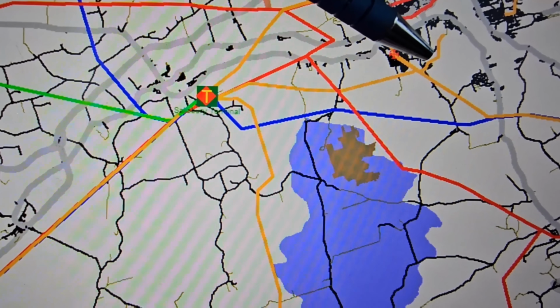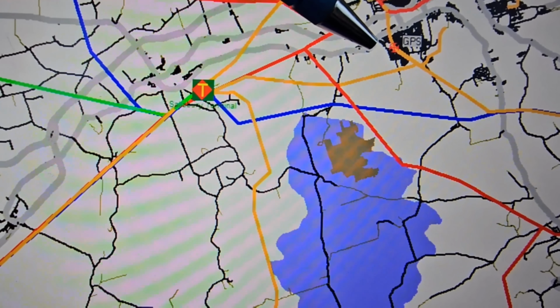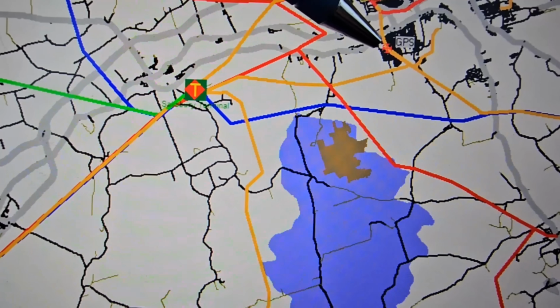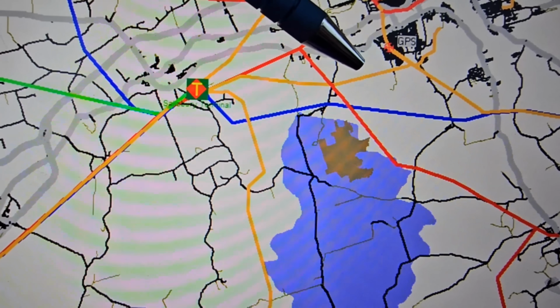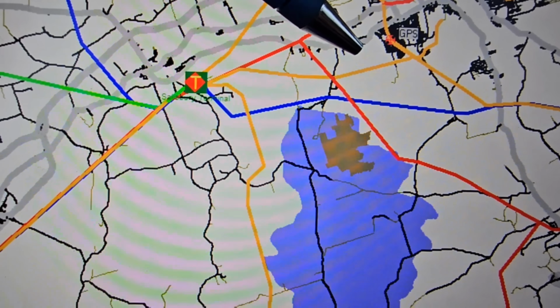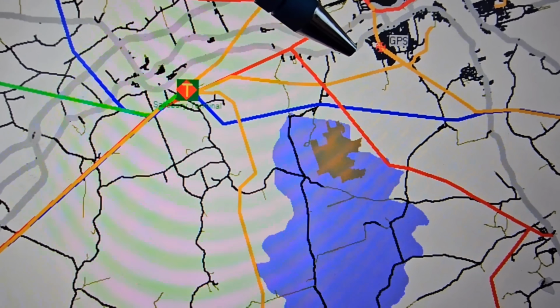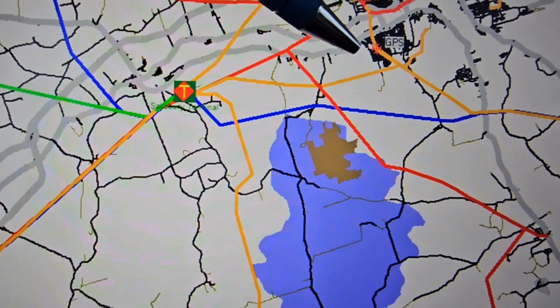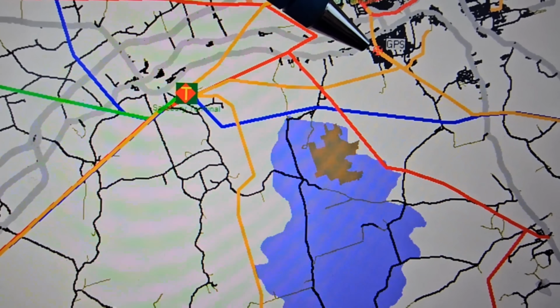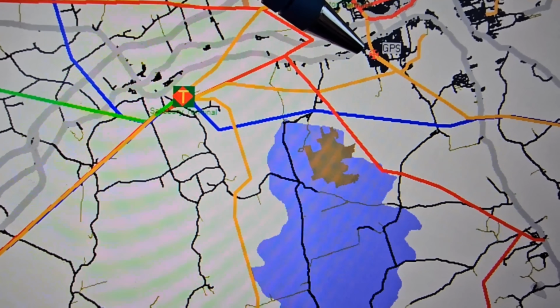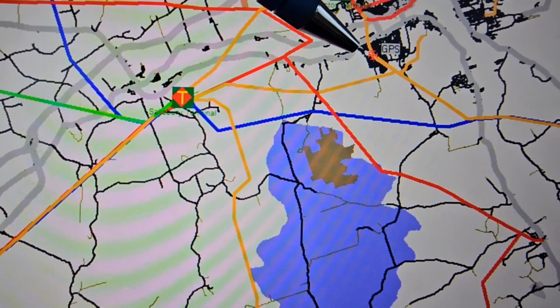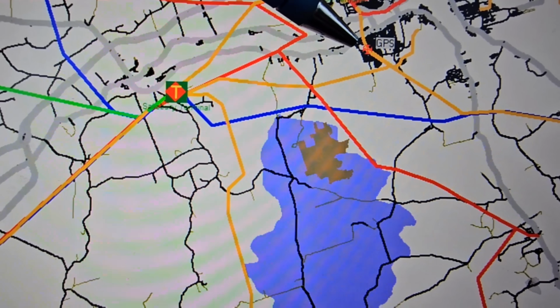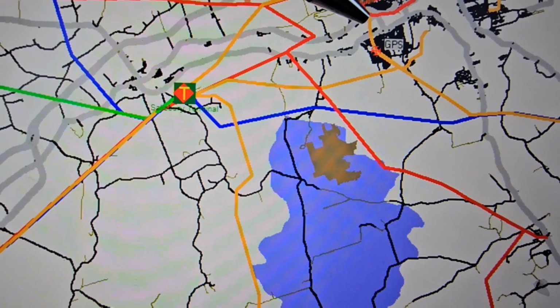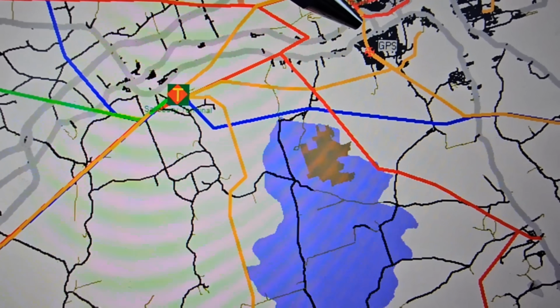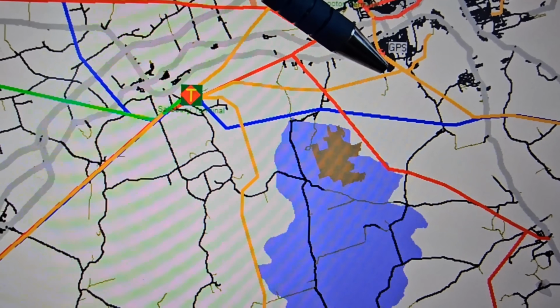The first thing we tried—when the power goes out, it's on a fail-safe system, basically so the lines don't burn down. Sometimes, say if a tree hit the lines, it will trip the power, but the arc flash could burn the tree clear, in which case the line can be closed back in. So the first thing we attempted was to re-energize the line from head office, which did not work out.